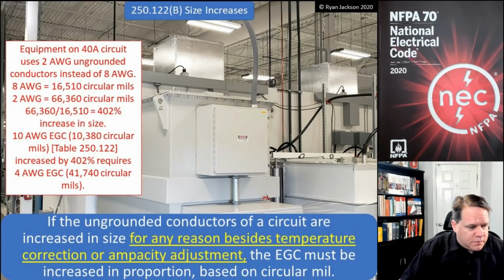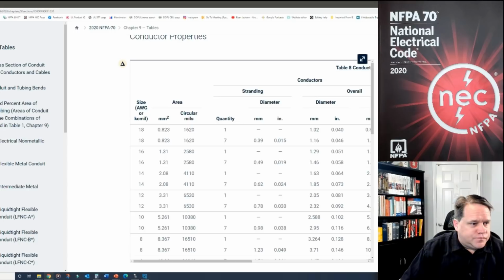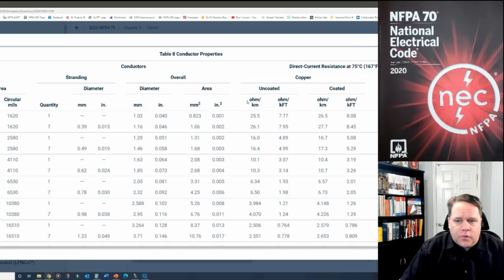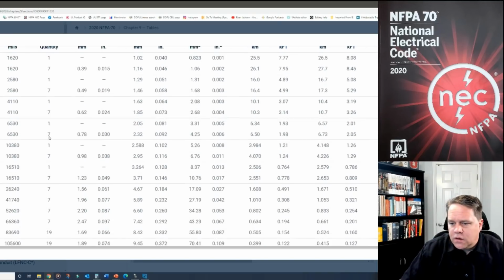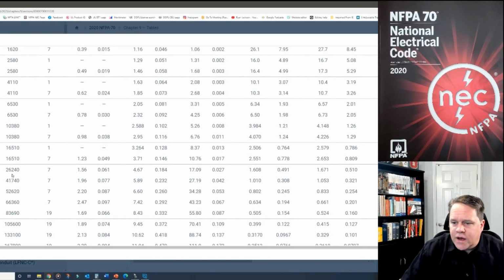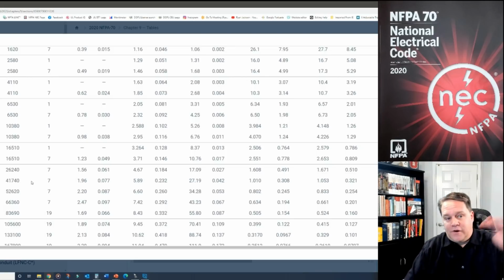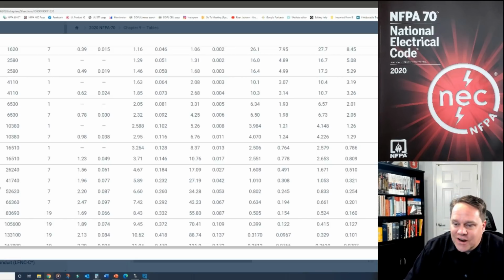So let's go ahead and bring the code book back up. Make this a little bit bigger so we can see it. I need 41,740. And as I scroll down, we can see that that would require a 4 gauge. And lucky us, the math worked out absolutely perfectly. So going from an 8 gauge to a 2 gauge actually yields the precise number needed. So that would be a 4 gauge equipment ground.